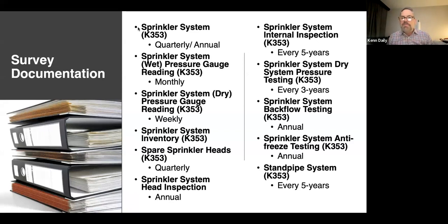And then a standpipe, if you have a standpipe, which some of you would know what that is, but you might know what FDC. If you have an FDC sign on the outside of your building, that's called a fire department connection. That's a standpipe. Standpipe is where a pumper truck could hook to your sprinkler system and add more water to your system. For whatever reason, they added that to your sprinkler system to add volume. Testing is done every 5 years. There's a hydrostatic pressure test that is done every 5 years on FDC connections.